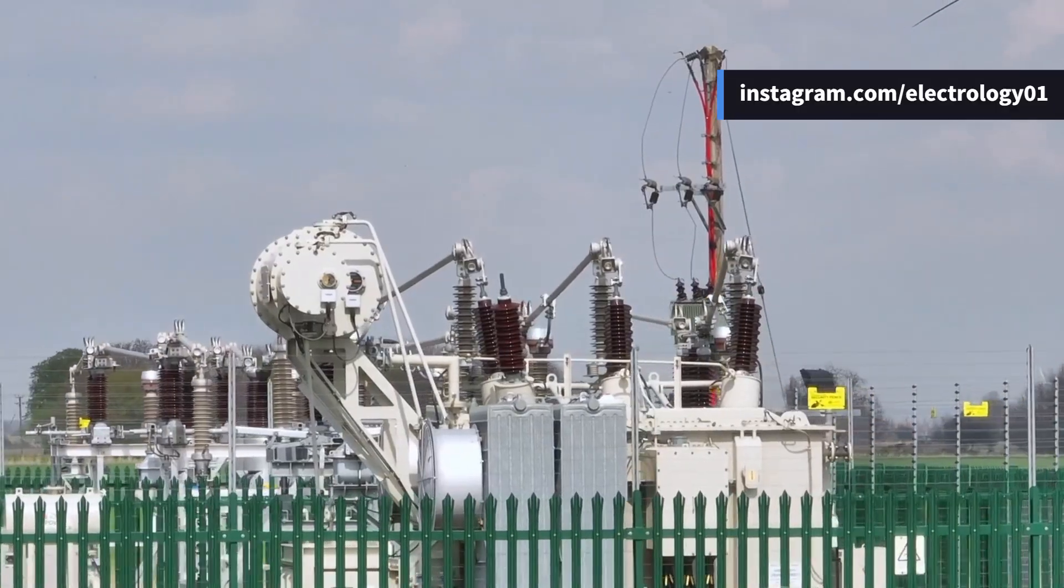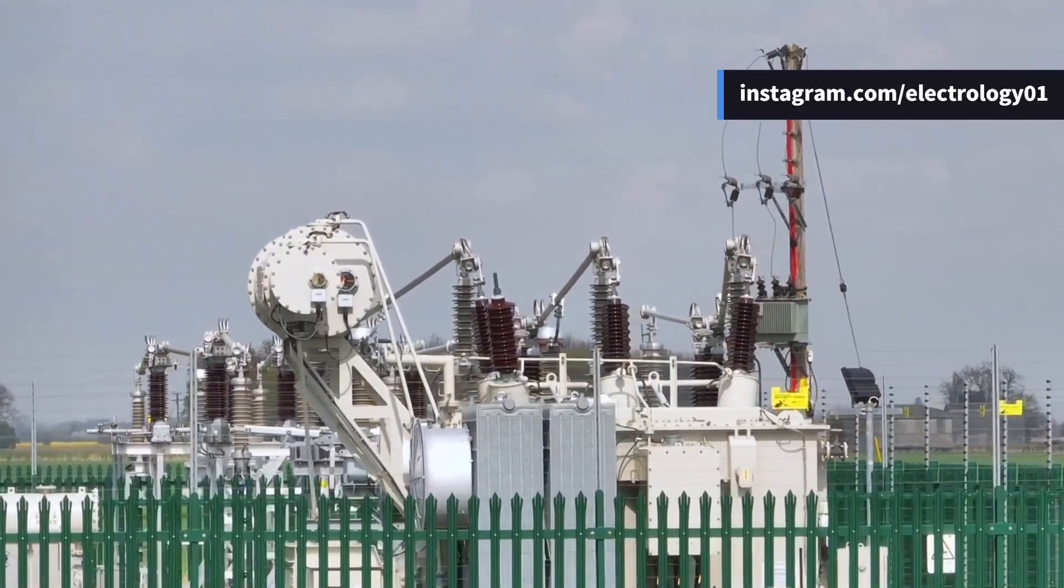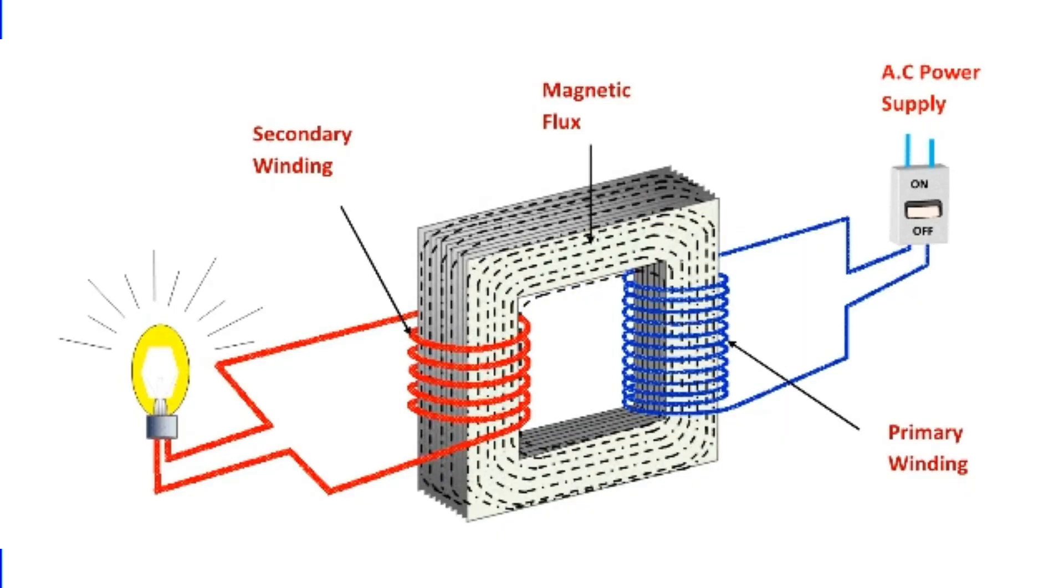First, let's understand what overfluxing means. A transformer is designed to operate at a specific magnetic flux level in its core. If this flux exceeds a certain limit, the core losses increase, leading to overheating and potentially causing internal faults. This is where overflux protection comes into play. It safeguards the transformer core from damage due to excessive flux.